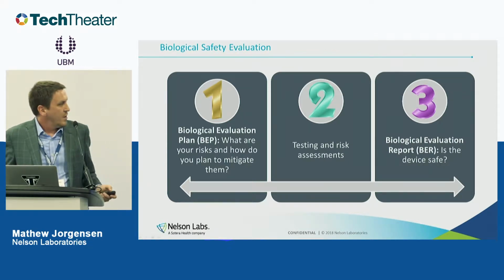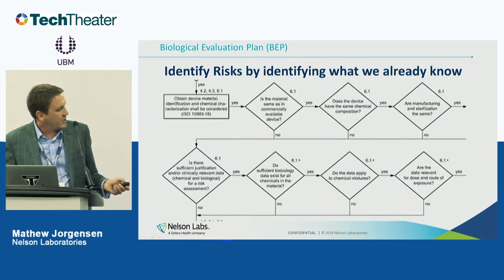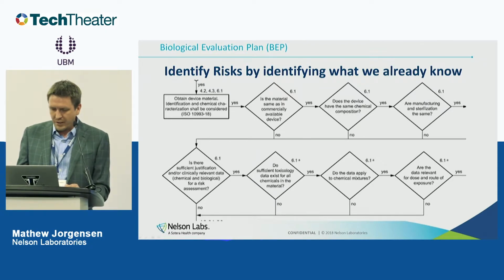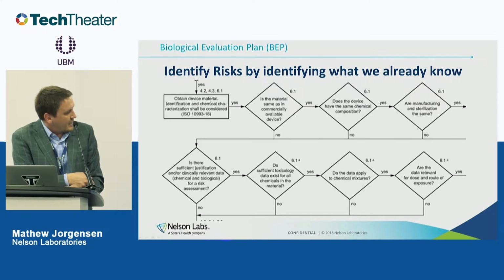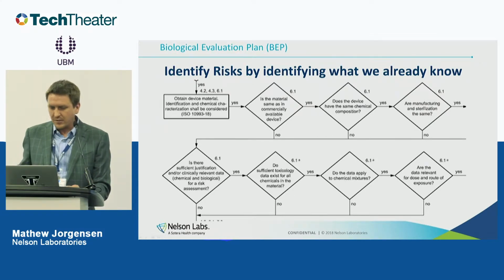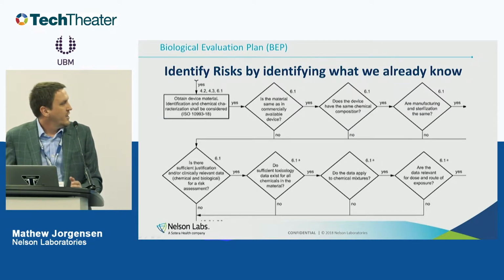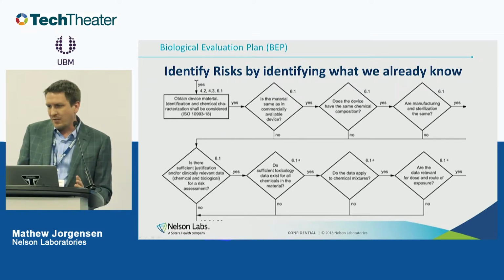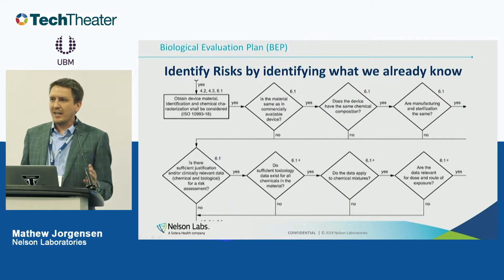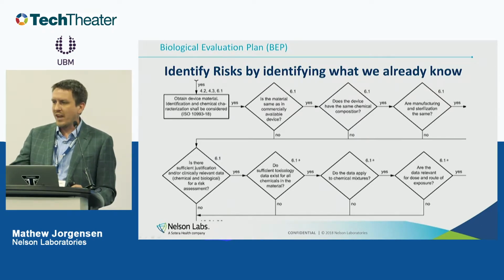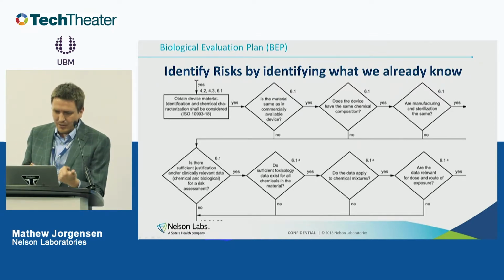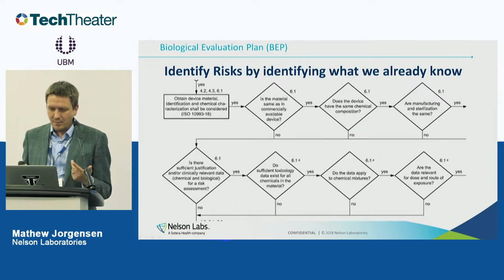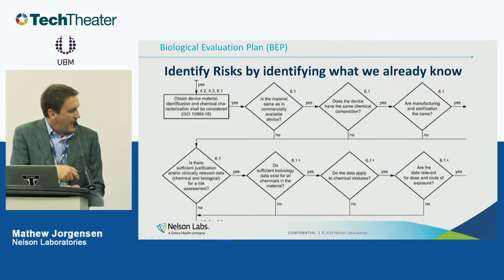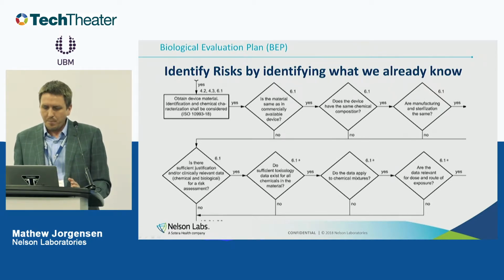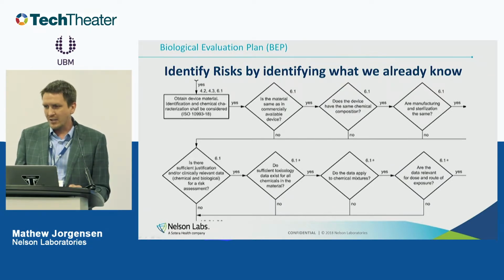So one of the things, as we go through this biological evaluation plan, is we start by identifying the risks. And you have a nice guide for this right in 10993-1 where you can ask yourself some of these questions. I encourage you to go through this flow chart later, where you're really trying to decide if you need to test. If you're going to test, you almost need to defend the fact that you had to test. So it's like, are you sure you need to test? Is the material the same as something that's already commercially available? Does the device have the same chemical composition and so on? If you can't answer those questions, then you do have to test. But it means that you can't just test blindly. If you test unnecessarily, you might need to be able to defend that.